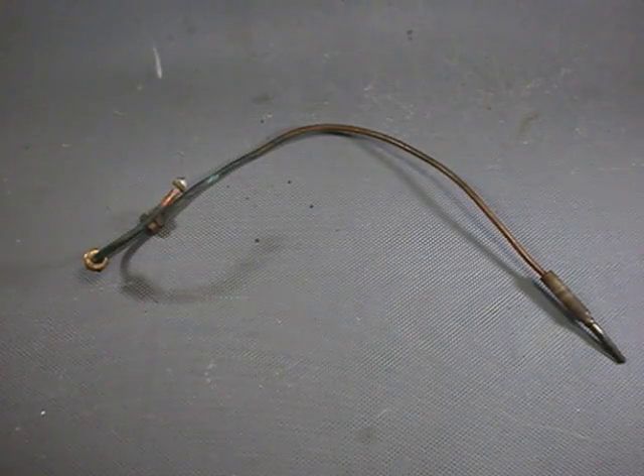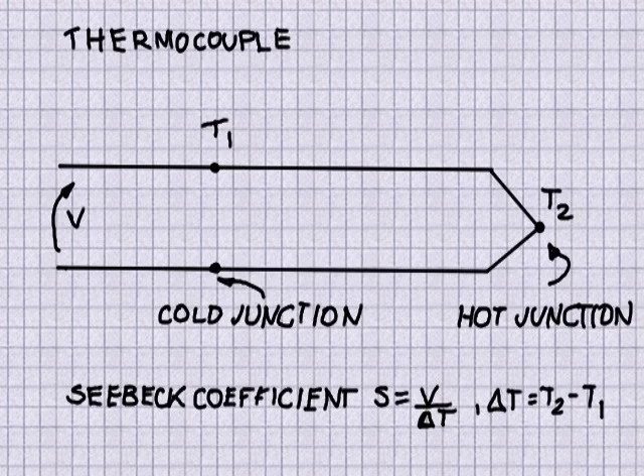This is a thermocouple of the type used with gas safety valves. A thermocouple is a transducer that converts heat into electrical energy by what is called thermoelectric effect. In particular, the voltage produced by a thermocouple is a function of the temperature at its hot junction.